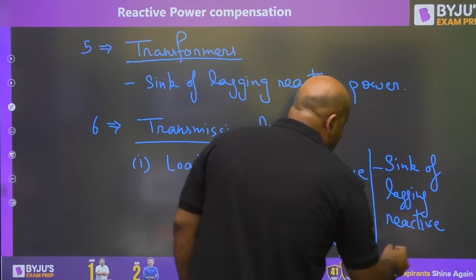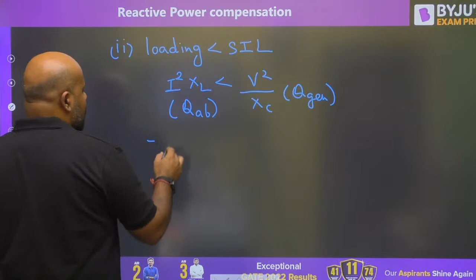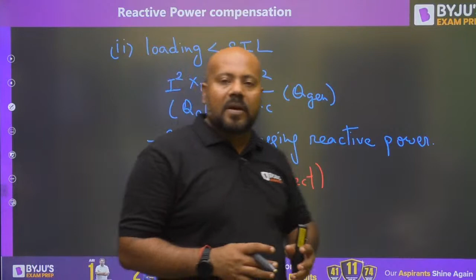The second condition is when the loading is less than surge impedance loading, the reactive power absorbed is less than the reactive power generated. This is the reactive power generated and this is the reactive power absorbed. So what is going to happen? It is going to act as a source of lagging reactive power. And this is the condition because of which you get the Ferranti effect. This is the reason why you are getting the no load or light load condition receiving end voltage more than the sending end voltage, because your line is acting as a source of lagging reactive power.